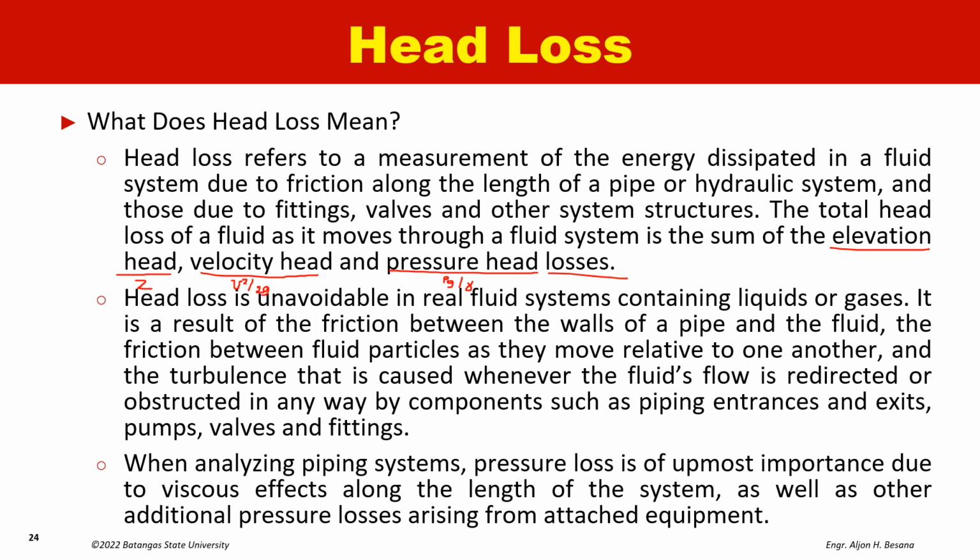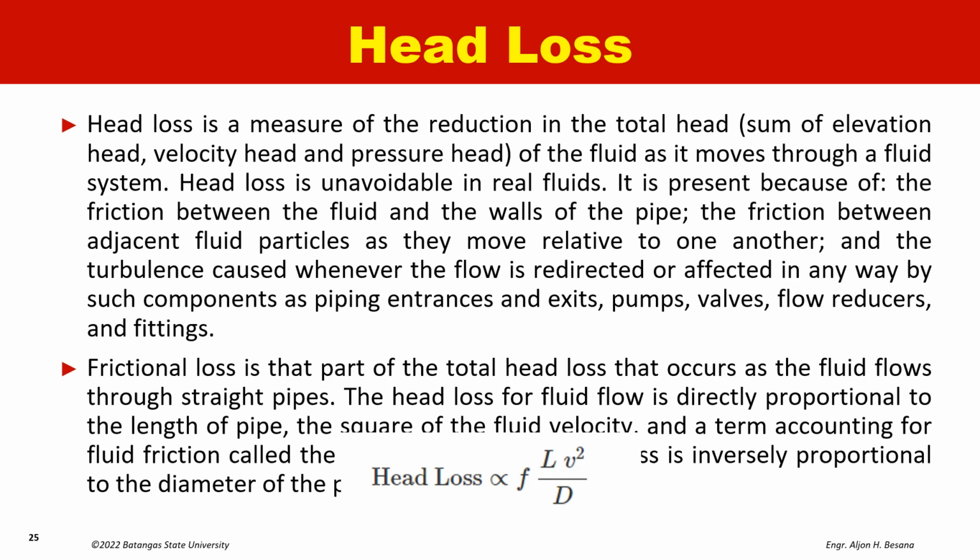Head loss is unavoidable in real fluid systems containing liquid or gases. It is a result of the friction between the walls of a pipe and the fluid, and the turbulence that is caused whenever the fluid flow is redirected or obstructed in any way by components such as piping, entrances and exits, pumps, valves, and fittings. When analyzing a piping system, pressure loss is of the utmost importance due to the viscous effects along the length of the system, as well as other additional pressure losses arising from the attached equipment.